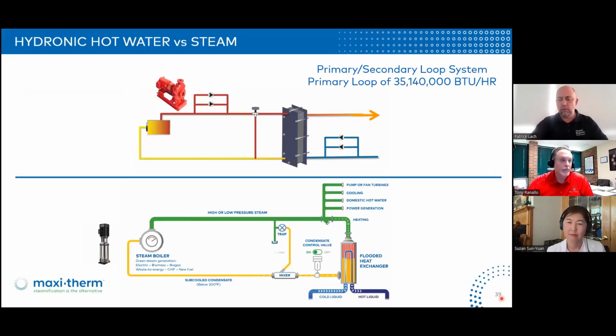Okay, let's go through a small, quick hydronic versus steam, because a lot of people think the hot water is more efficient. So keep in mind what Tony has presented earlier, 95% efficiency possible with a steam boiler. And by the way, if you install the vertical flooding design everywhere in the city, in the campus, and the building, this becomes 100% closed loop. So no more de-aerator, gone. Chemical costs down, surface blowdown. There's a lot of savings. You don't need a de-aerator anymore, just a feed water tank. You don't have any fresh water, very, very minimum, right?